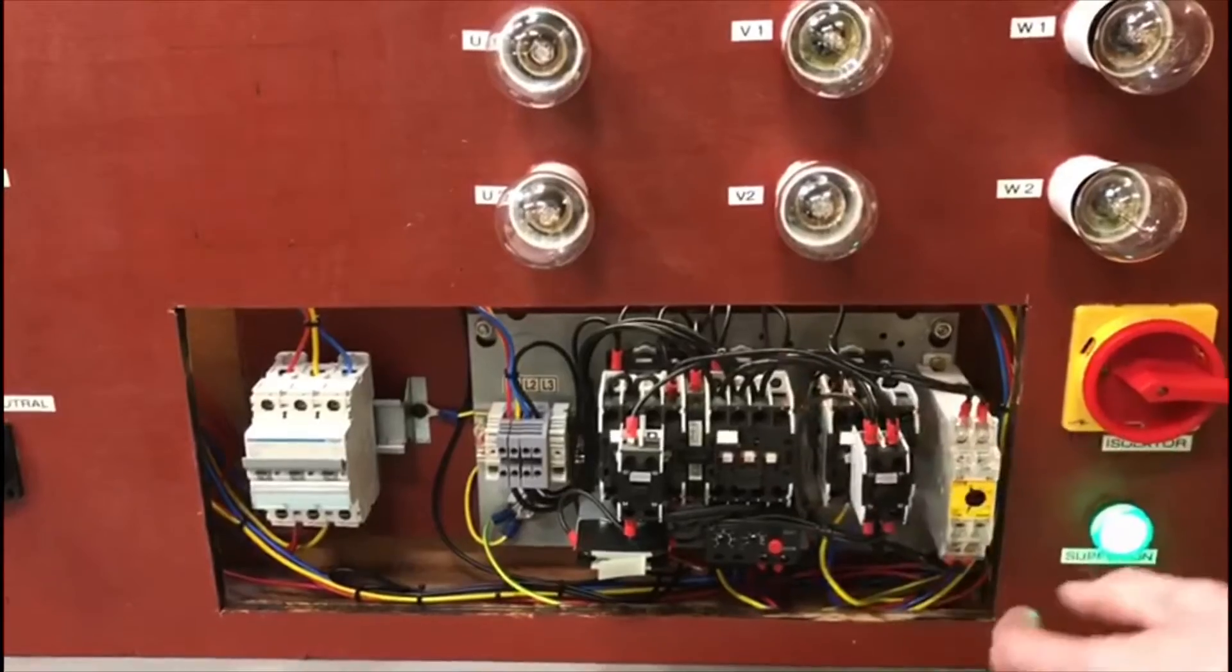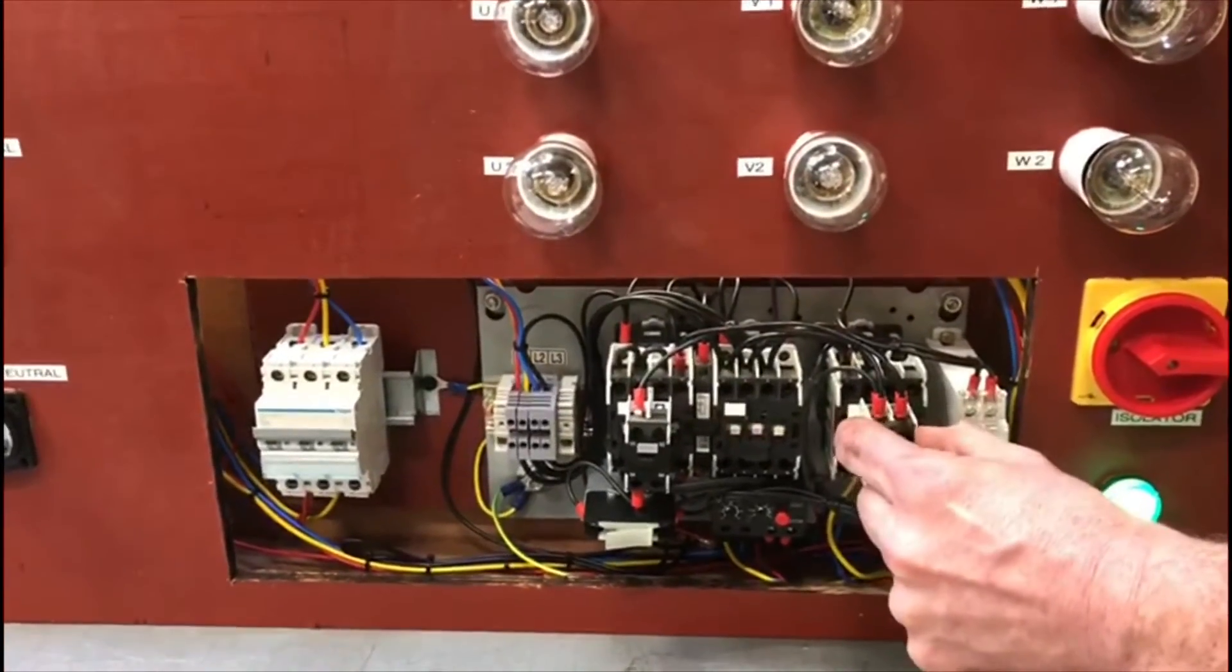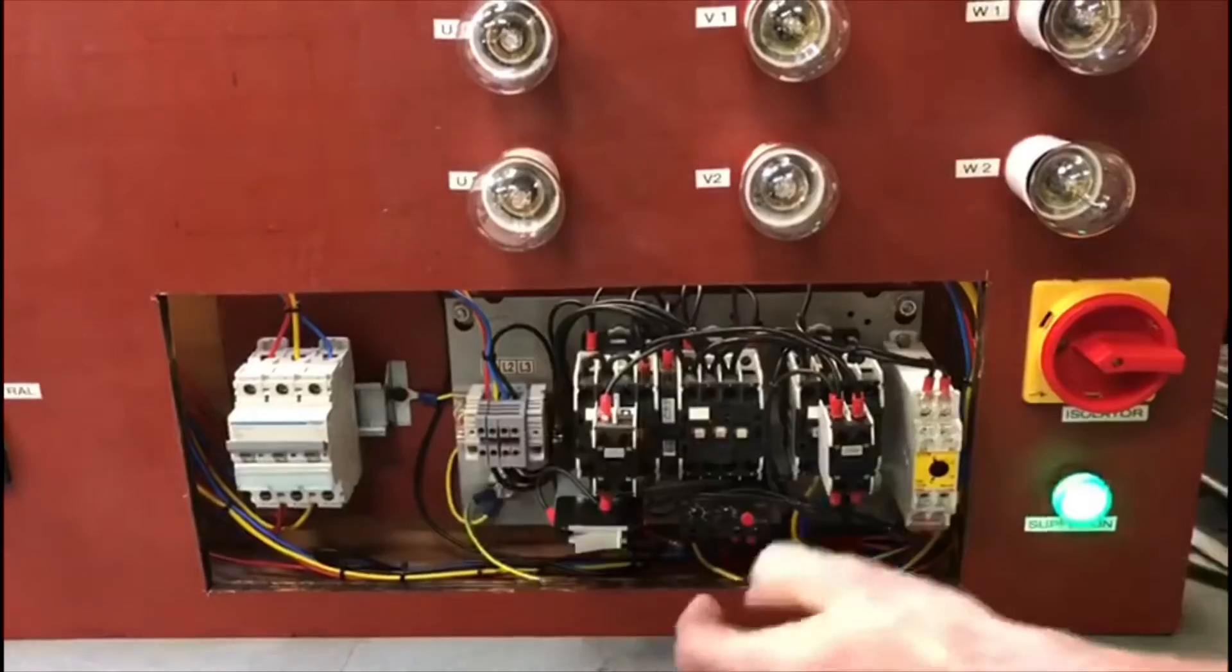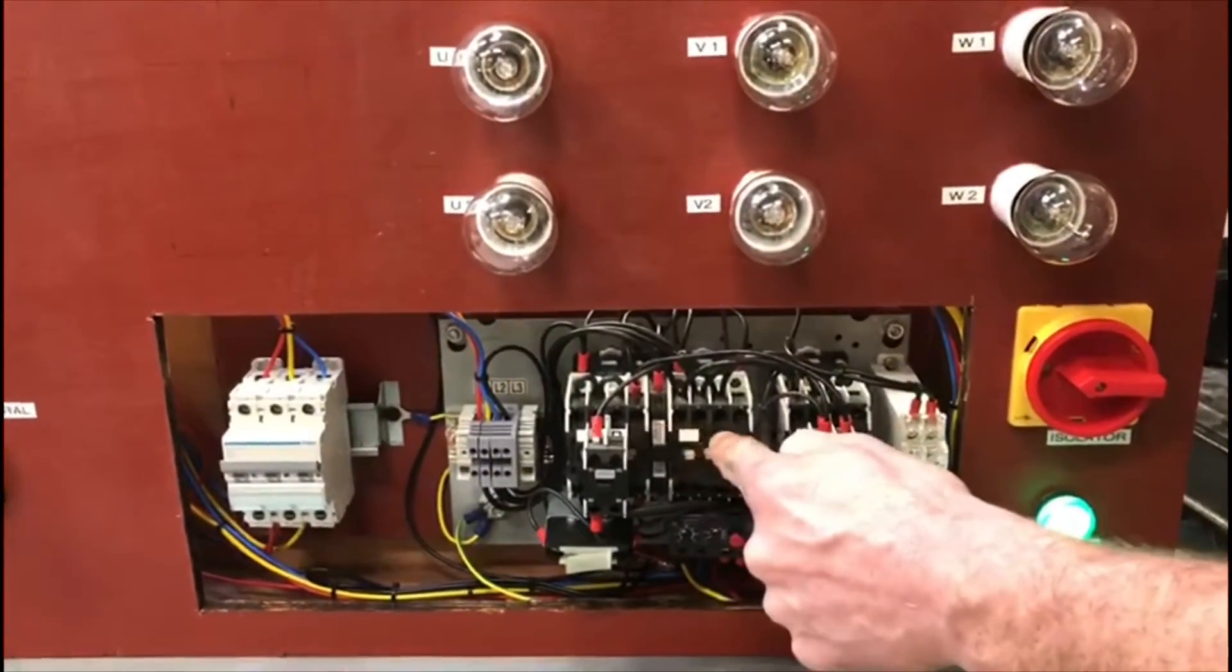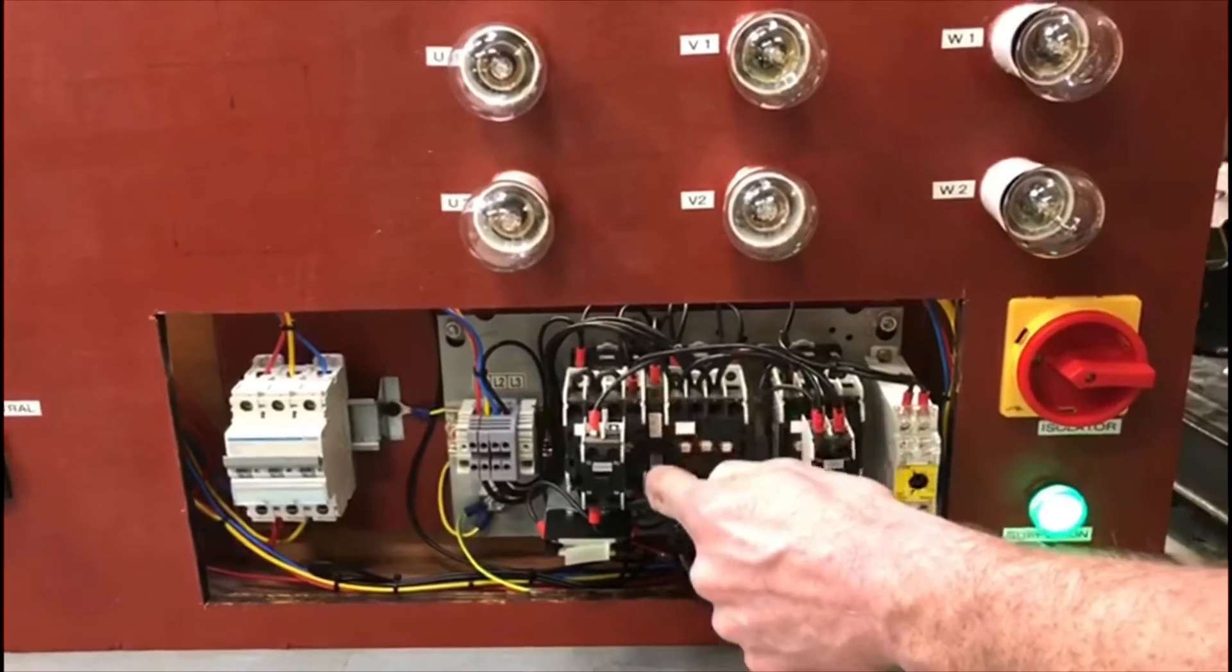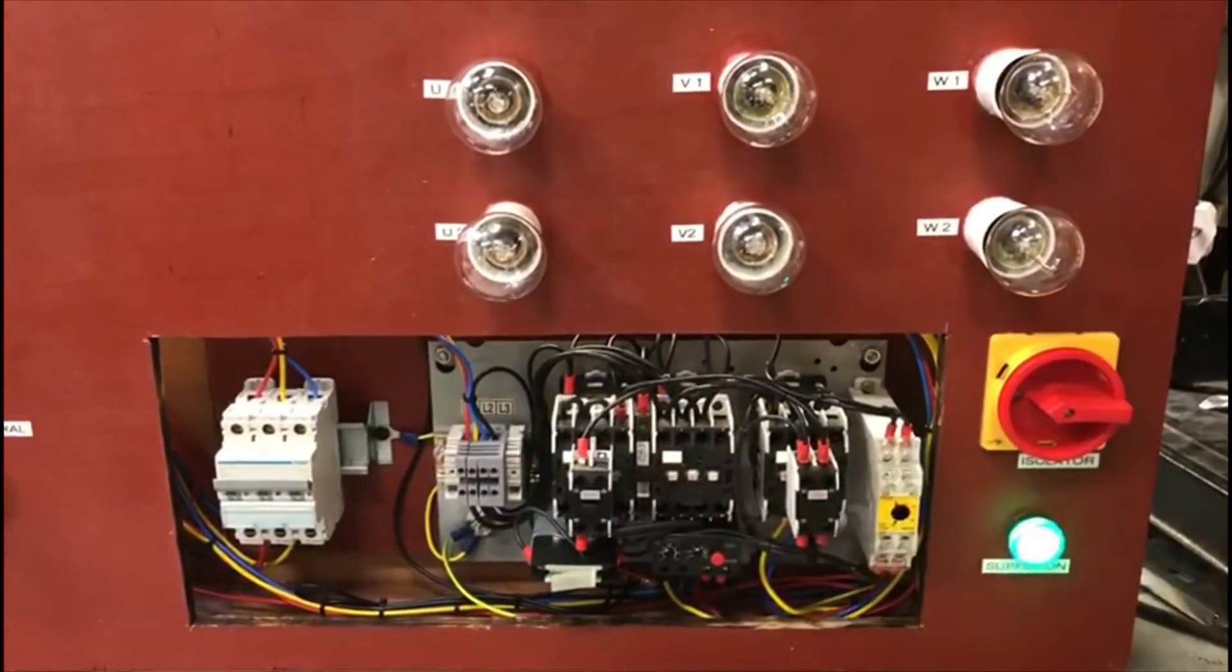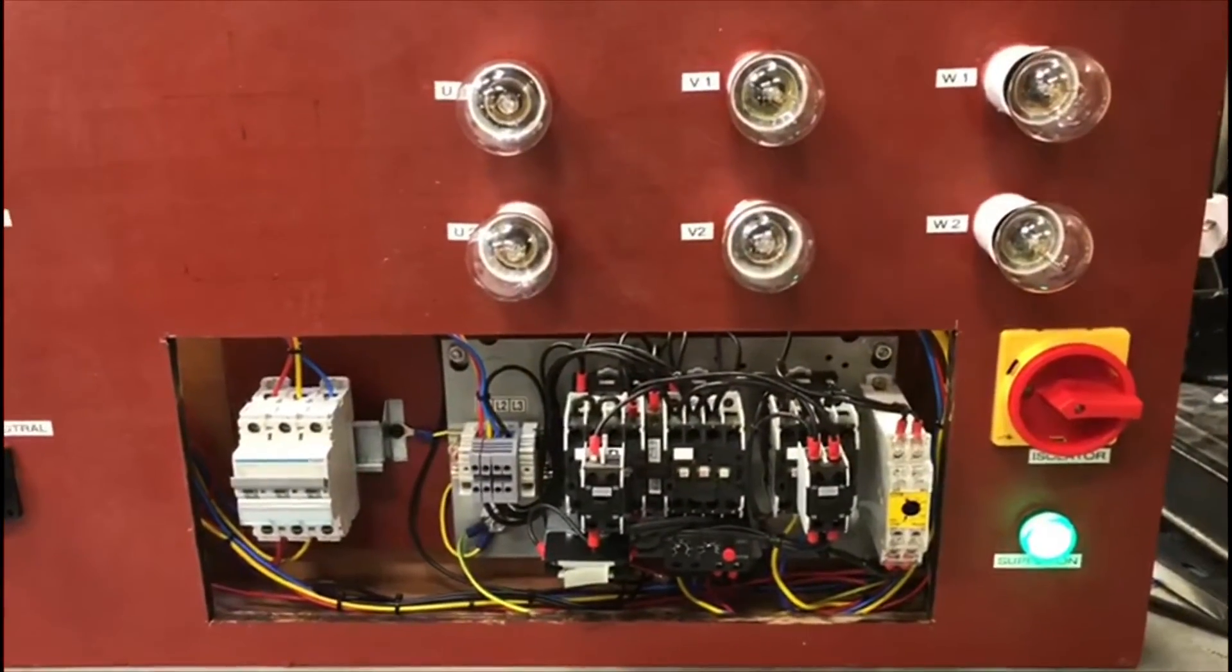The main contactor will also remain energized and remain pulled in at all times. So I'll just say that again: we've got the main contactor. As we start it, this one pulls in. After about 20 seconds due to the timer, this one will pull out and this one will pull in. There's an interlock in the middle to prevent both of them being energized at the same time.